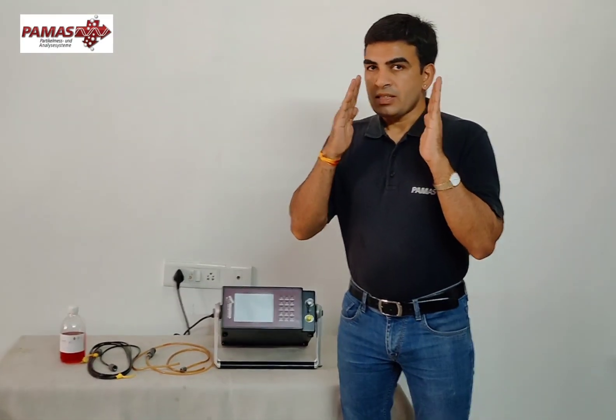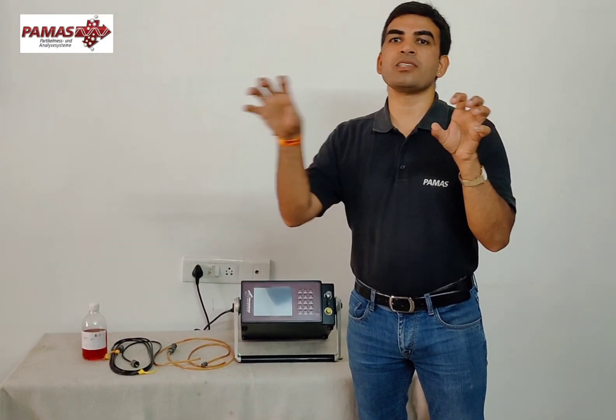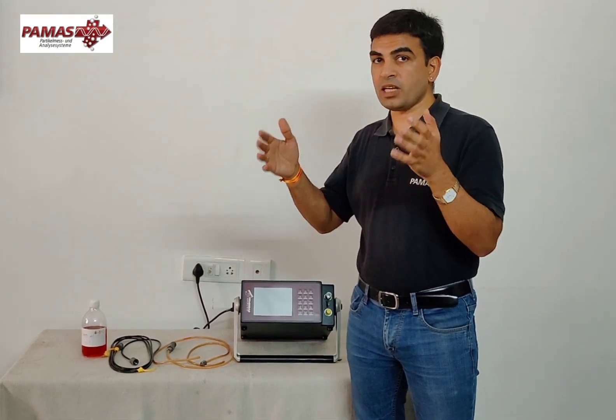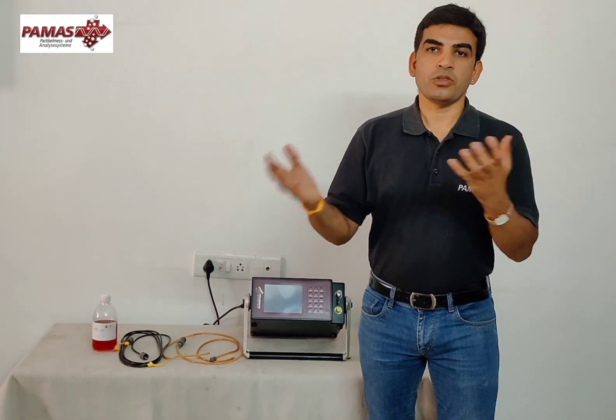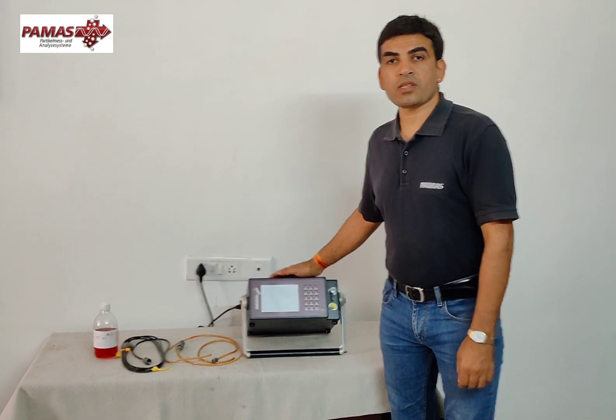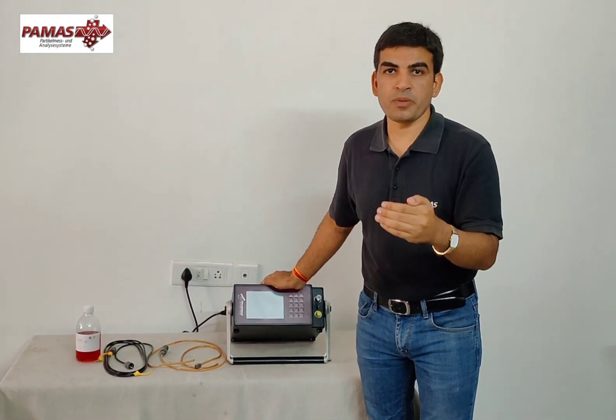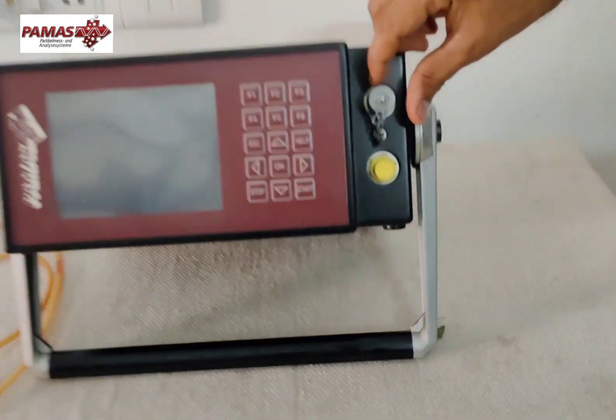There is no conversion between standards. If you have only one calibration and get a report in a different calibration, that is just an approximation. In this instrument there is no such approximation — you get accurate data as per the standard. You don't have to keep two instruments. If some machines follow NAS and others follow ISO, you just use this one single instrument with both calibrations. It is capable of giving you almost every international standard report: ISO, NAS, SAE, GOST, GJB, and many others.